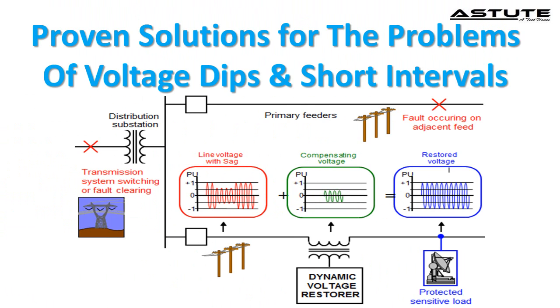There are different ways available to recover from the voltage dips entering the device, given below. Use of tap changing transformers. Use a static voltage regulator. Ferro-resonant transformers. Uninterruptible power supplies, battery storage, flywheels and motor generator sets. Compressed air energy storage. A dynamic voltage restorer is used to restore the voltage. Use electronic voltage regulators. For three-phase equipment, use magnetic synthesizers.